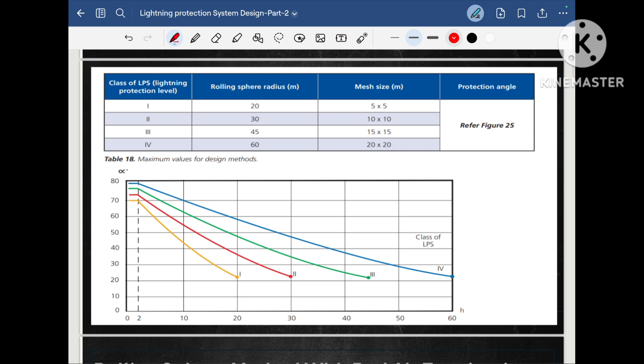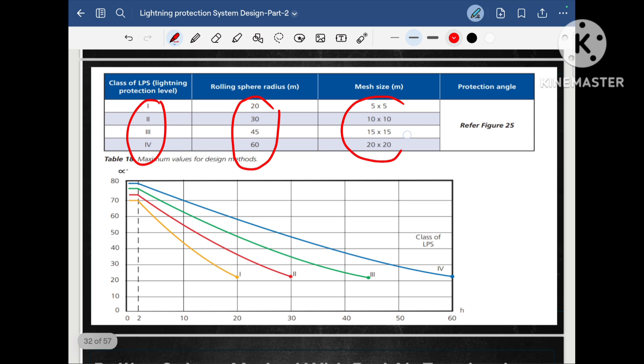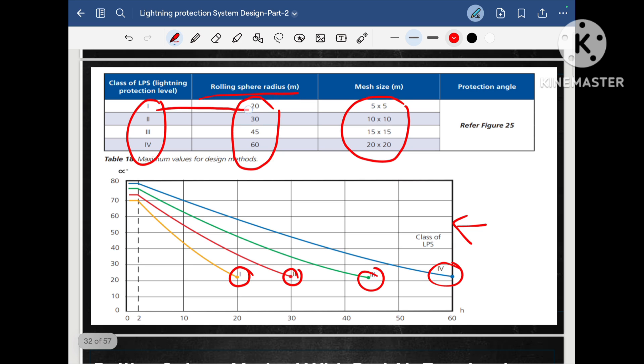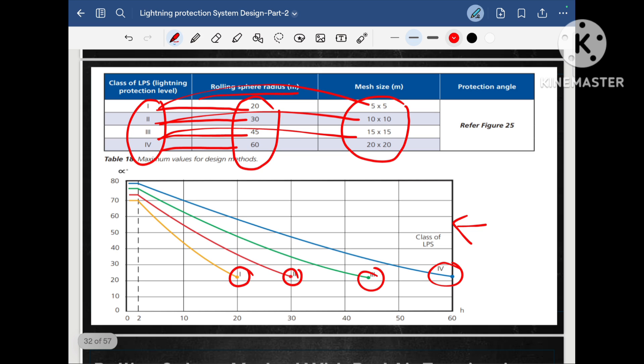There is a table showing that for class 1, class 2, class 3 and class 4 lightning protection systems, what the rolling sphere radius and mesh size would be for each respective class. For the rolling sphere method: class 1 radius is 20 meters, class 2 is 30 meters, class 3 is 45 meters, and class 4 is 60 meters — as per IEC standard. For mesh size: class 1 is 5×5 meters, class 2 is 10×10 meters, class 3 is 15×15 meters, and class 4 is 20 meters.